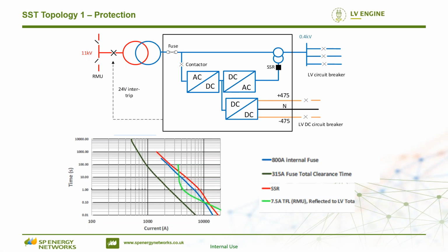One of the most important things of this unit is the protection. So the unit is protected by a fuse, and that fuse should be in coordination with what we have on our main unit, and also on an LV AC board. But this unit should also be protected when a fault happens. So there's a high current going through this route, which can induce high voltage on the secondary side or primary side of the coupling transformer.